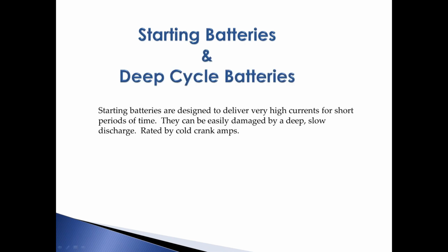There are a couple of different types of batteries you run into. Starting batteries are the ones you're used to having in a car or truck, designed to start your car, delivering very high currents to the starter motor for fairly short periods of time, measured in seconds usually. They can be easily damaged by a deep, slow discharge because they're not built for that, and you'll find them rated by cold crank amps.